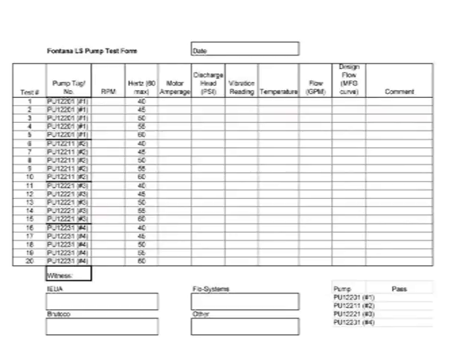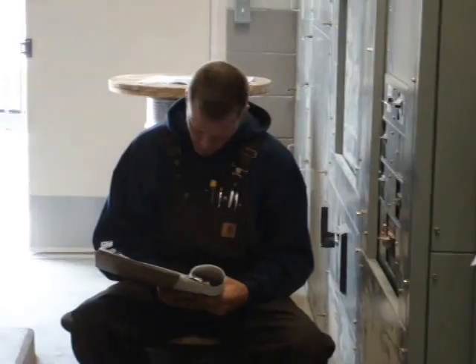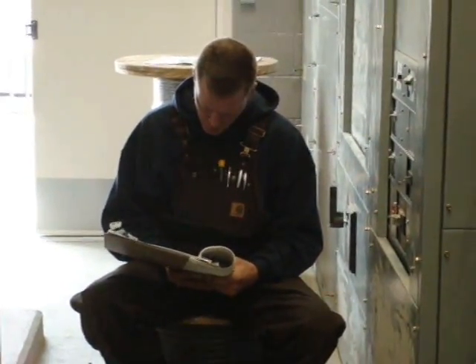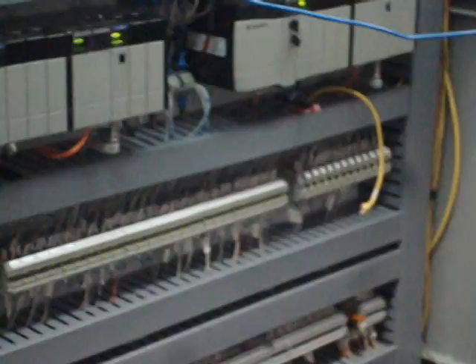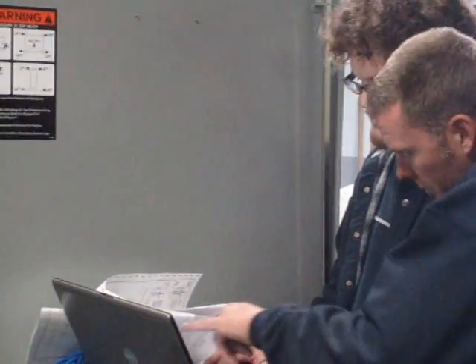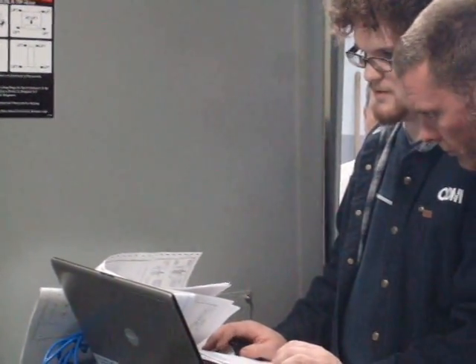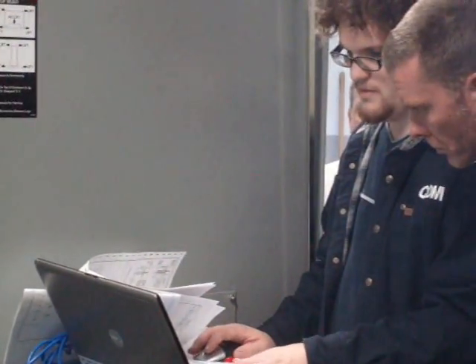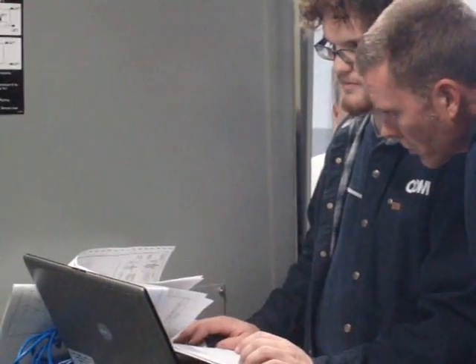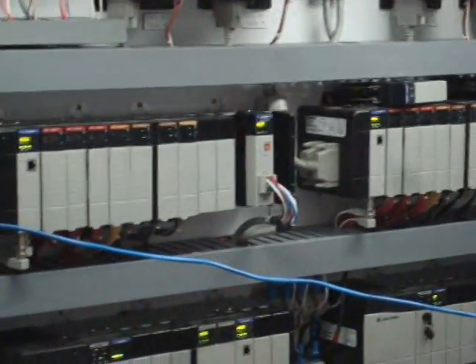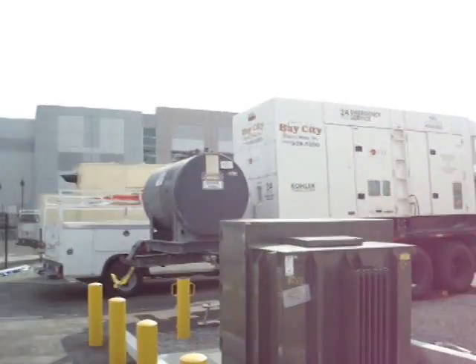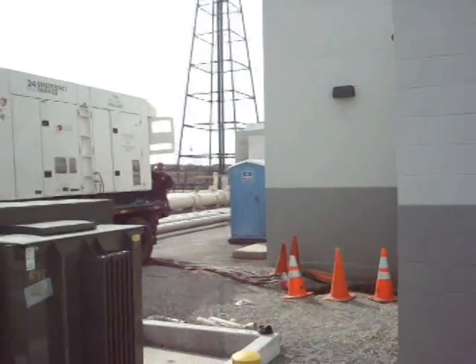This is the form we use to record all the data on the flow test for each of the pumps from 40 Hertz to 60 Hertz. We're looking at setting up the Modbus system here, where we have automatic communication from the PLC to the VFDs, and communication here is by way of Modbus, but it ultimately ends up in SCADA and it's controlled remotely. This is an Allen Bradley PLC system.